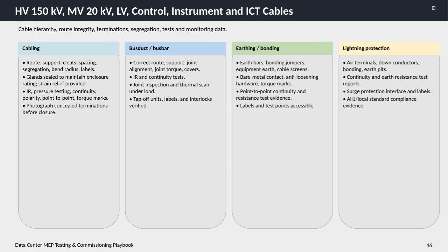Finally, lightning protection involves air terminals, down conductors, bonding, and earth pits to safely dissipate any lightning strikes. Continuity and earth resistance testing are critical, along with documentation of surge protection interfaces and labels. Compliance with the authority having jurisdiction and local standards is vital to ensure overall safety and regulatory adherence. These detailed checks and documentation form the backbone of a robust, safe, and reliable data center MEP system.